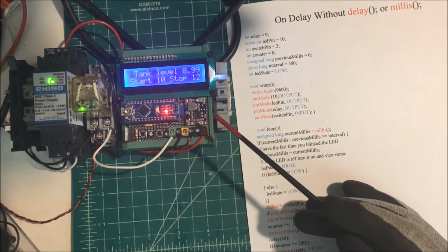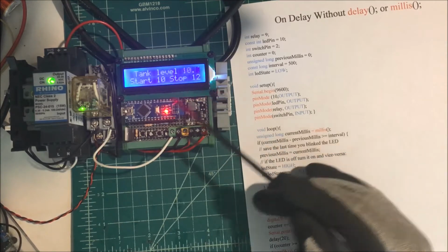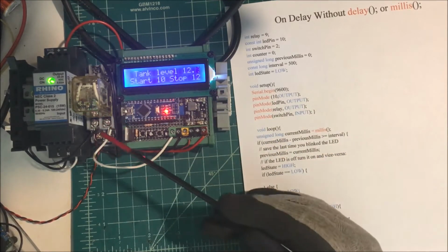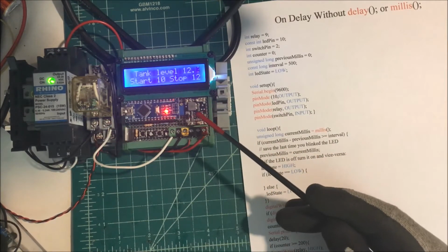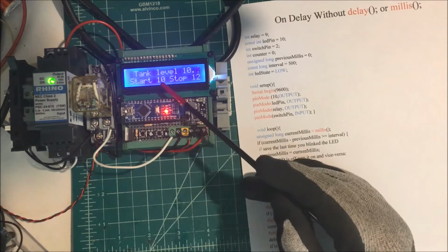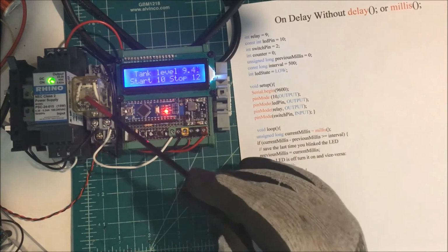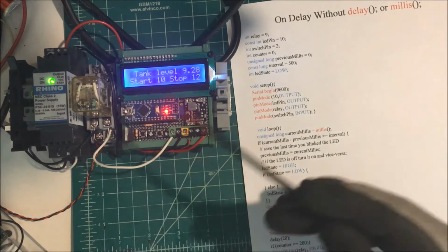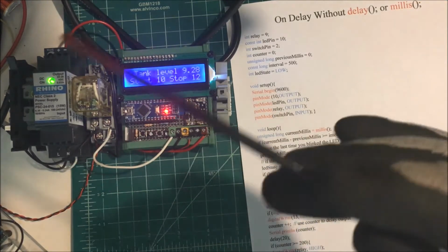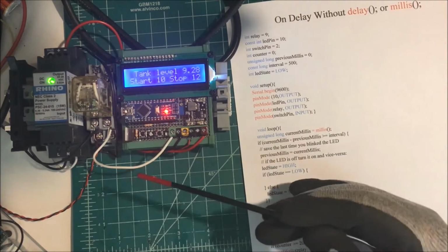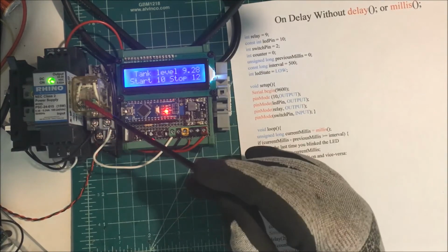Now, if I move this up to 12, this relay should turn off. It does. And as you bring this back down to 10 feet, now, there you go. I don't want this to come on right away. When you turn off the well, you want to wait a little bit, give it time for the column of water to drop down before you start the well back up.